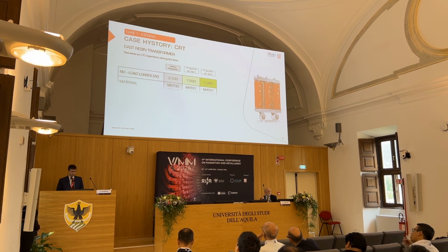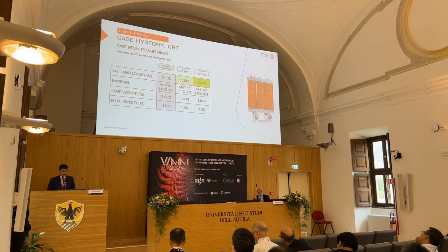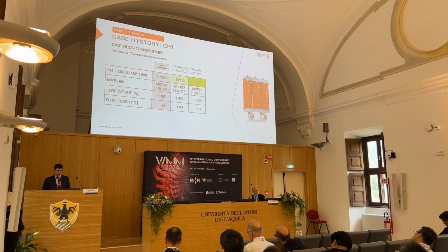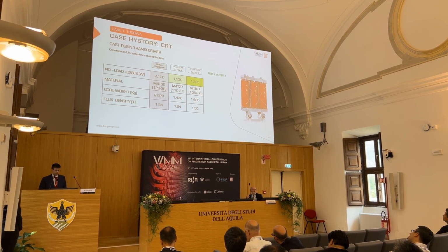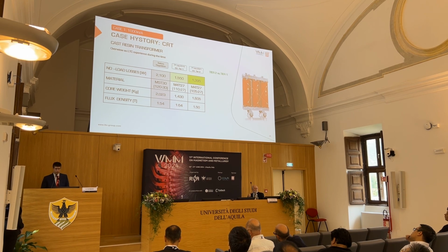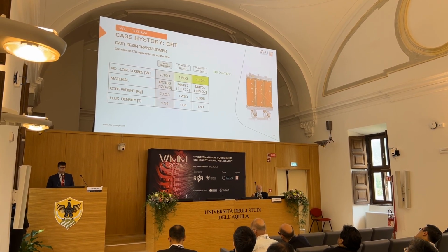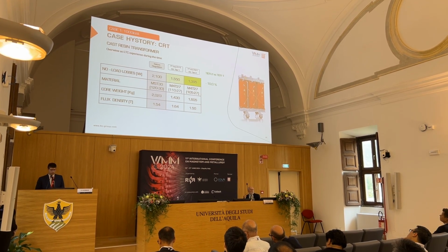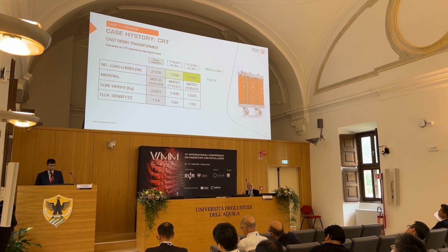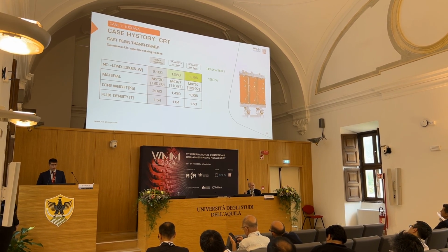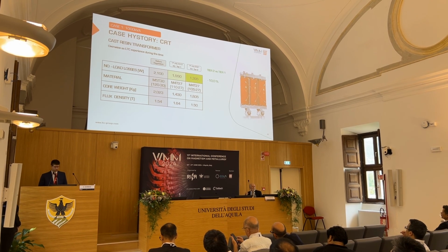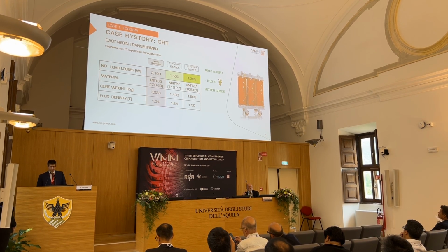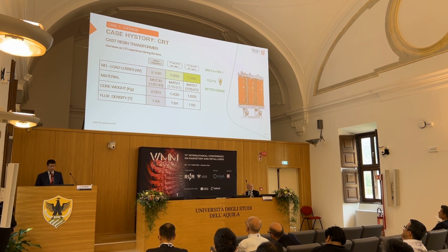We can see it in the CRT type, the cast resin transformer. We have 1000 kVA. In this case, the material is no longer a laser material, but a conventional material. Before the regulation, the most common material was M5030 with a specific loss of 1.20 watt/kg. Due to the regulation, there is a big reduction in losses between before the regulation and Tier 1, and then between Tier 1 and Tier 2 the change is, let's say, 10%. What is different here in the design is that the material is changed to a selection of M4027.